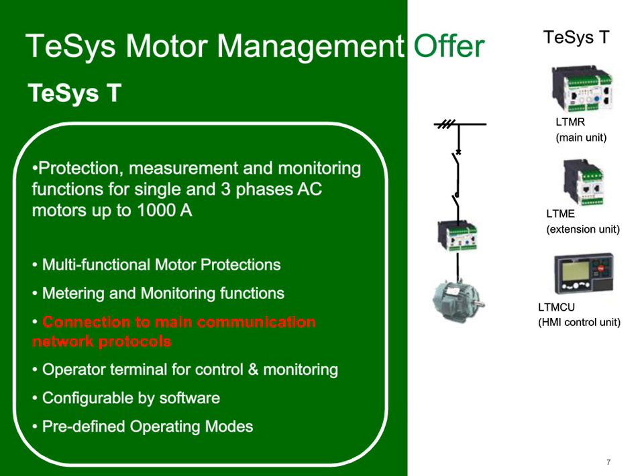So if we say what capabilities does this product actually provide us for those processes that are controlled by electrical motors, we can actually have motor protection. We can actually meter or monitor the functions that the motors are controlling. Very, very important here is these units actually communicate over industrial protocols and now over Ethernet protocols. We do have abilities now for putting terminals or monitors here that take this data and put it in useful information like SCADA systems or building automation systems.